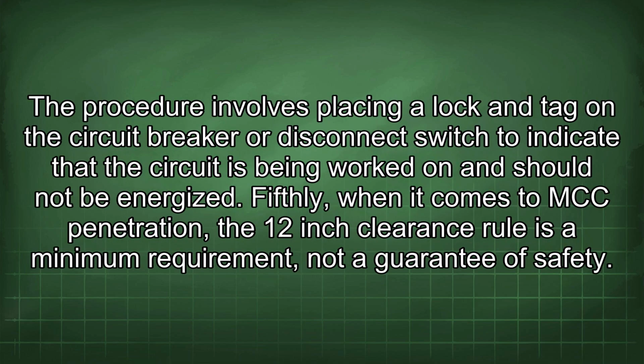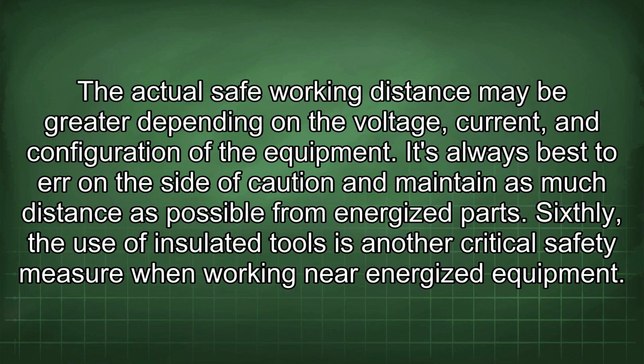The procedure involves placing a lock and tag on the circuit breaker or disconnect switch to indicate that the circuit is being worked on and should not be energized. Fifthly, when it comes to MCC penetration, the 12-inch clearance rule is a minimum requirement, not a guarantee of safety. The actual safe working distance may be greater depending on the voltage, current, and configuration of the equipment. It's always best to err on the side of caution and maintain as much distance as possible from energized parts.